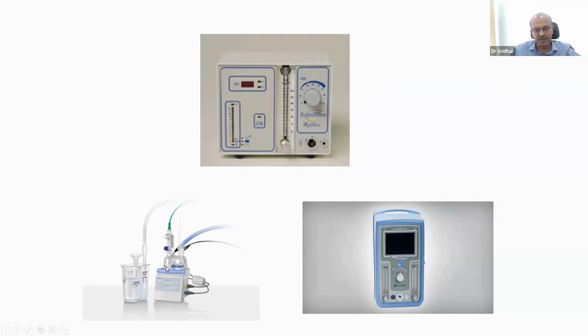This is the bubble CPAP. I mean, when we discussed indigenous CPAP, when I was training and we didn't have a proper CPAP unit, this is literally what we used to do, but in a non-technical way. So we used to have the Y connection with air and oxygen, and we used to have an underwater bottle. The depth of the tube immersing into it, it's something similar to what we used to drain the pneumothorax with underwater seal. But we didn't have humidification for that, and now with the bubble CPAP, we have a proper setup with the humidity and everything else, and the depth of insertion will control the CPAP level.